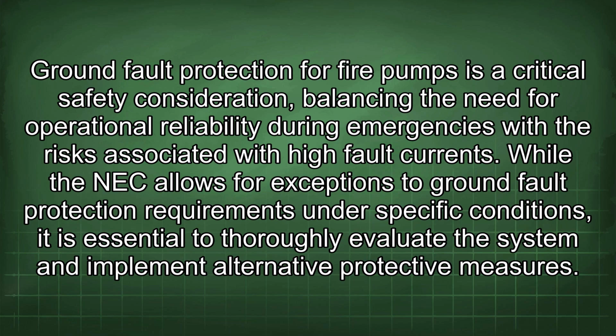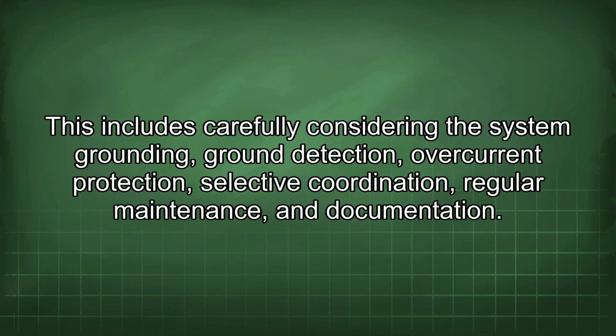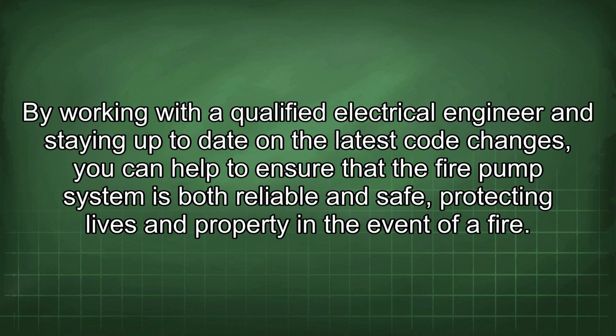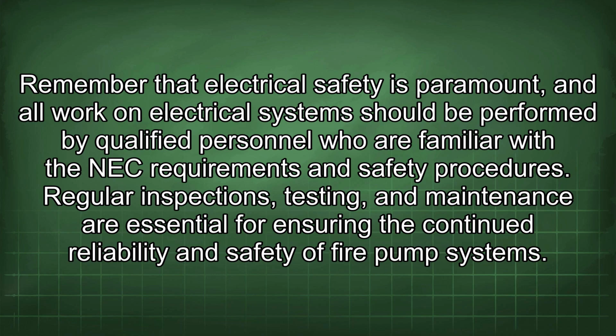Ground fault protection for fire pumps is a critical safety consideration, balancing the need for operational reliability during emergencies with the risks associated with high fault currents. While the NEC allows for exceptions to ground fault protection requirements under specific conditions, it is essential to thoroughly evaluate the system and implement alternative protective measures. This includes carefully considering the system grounding, ground detection, overcurrent protection, selective coordination, regular maintenance, and documentation. By working with a qualified electrical engineer and staying up to date on the latest code changes, you can help to ensure that the fire pump system is both reliable and safe, protecting lives and property in the event of a fire. Remember that electrical safety is paramount, and all work on electrical systems should be performed by qualified personnel who are familiar with the NEC requirements and safety procedures. Regular inspections, testing, and maintenance are essential for ensuring the continued reliability and safety of fire pump systems.